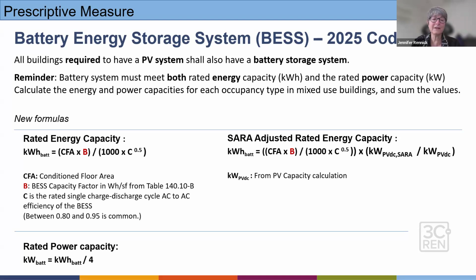It's now based on the conditioned floor area, using a factor B for your BESS, or battery energy storage system, from a different table. The rated power capacity is more simple - you just take that kilowatt hour value from the first formula, plug it into the second formula, and divide it by 4. So they simplified the rated power capacity.